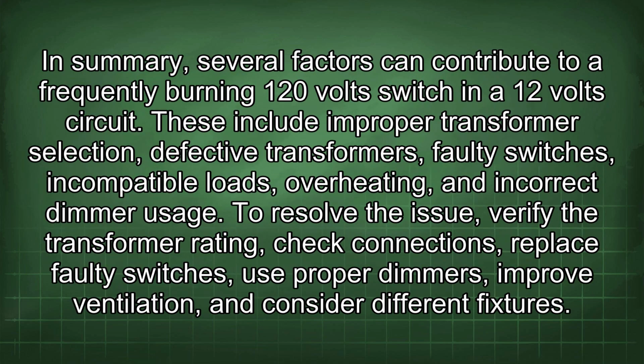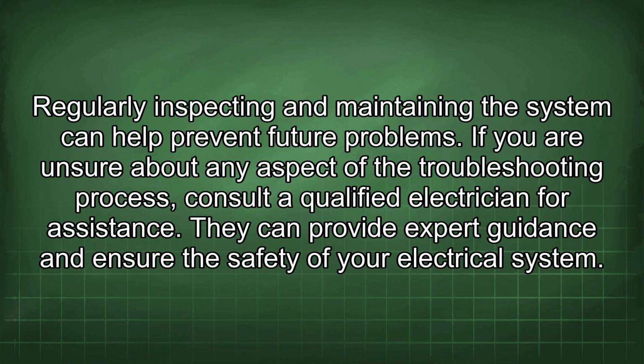In summary, several factors can contribute to a frequently burning 120-volt switch in a 12-volt circuit. These include improper transformer selection, defective transformers, faulty switches, incompatible loads, overheating, and incorrect dimmer usage. To resolve the issue, verify the transformer rating, check connections, replace faulty switches, use proper dimmers, improve ventilation, and consider different fixtures. Regularly inspecting and maintaining the system can help prevent future problems.